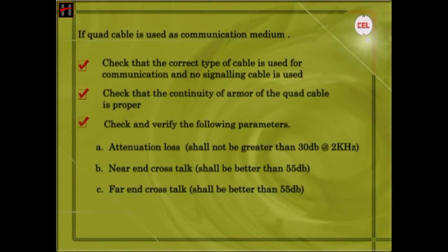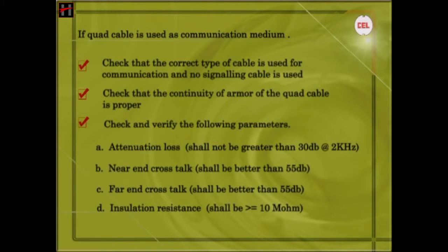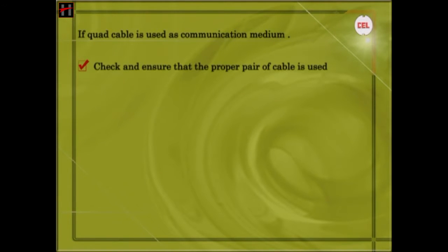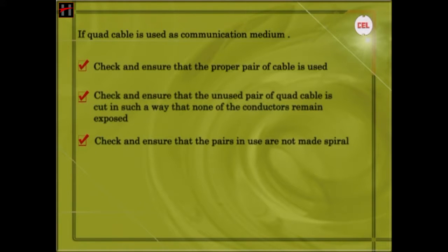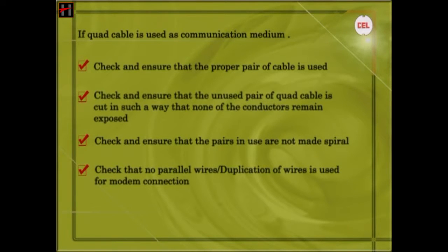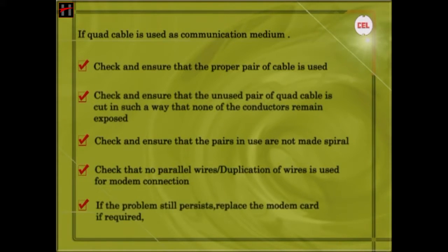The far end crosstalk shall be better than 55 dB, and the insulation resistance of the quad cable shall be greater than or equal to 10 mega ohms. Check and ensure that the proper pair of cable is used. Check and ensure that the unused pair of quad cable is cut in such a way that none of the conductors remain exposed. Check that the pairs in use are not made spiral, and check that no parallel wires or duplication of wires is used for modem connection. If the problem still persists, replace the modem card if required.